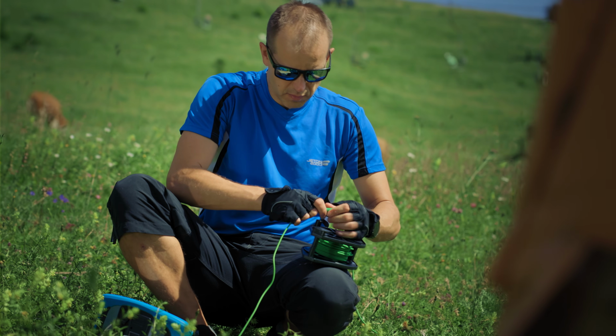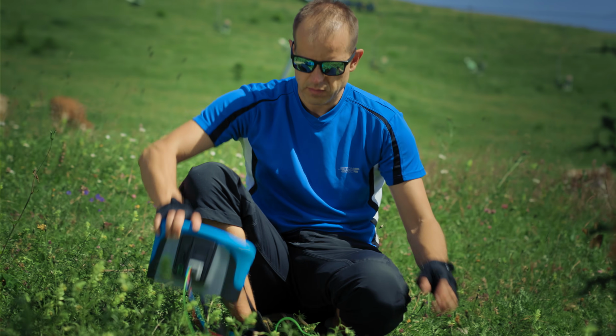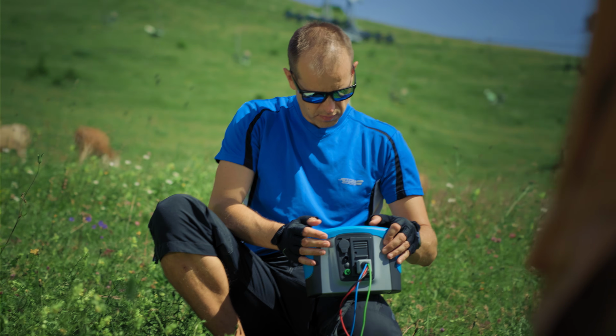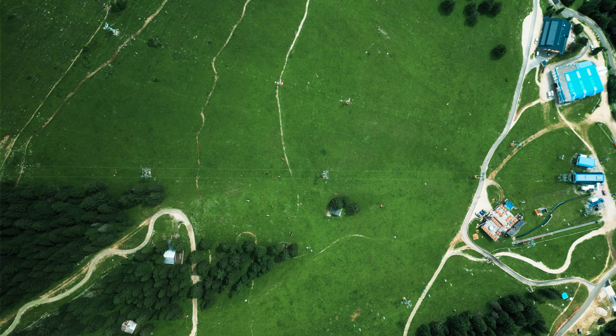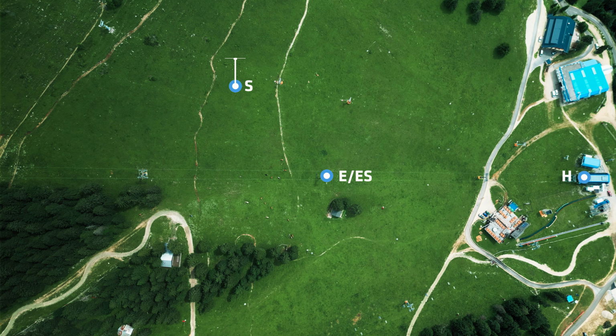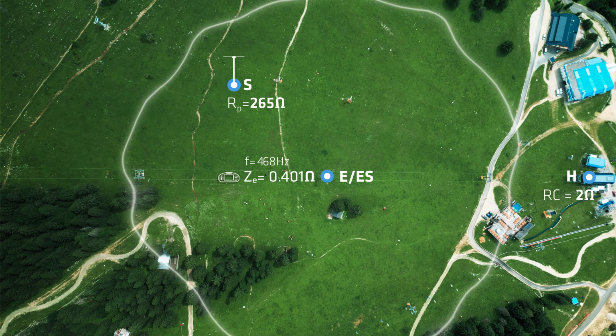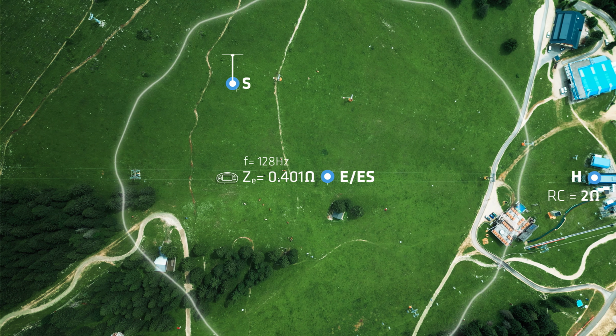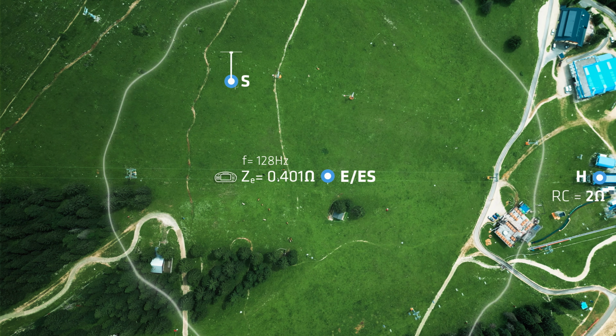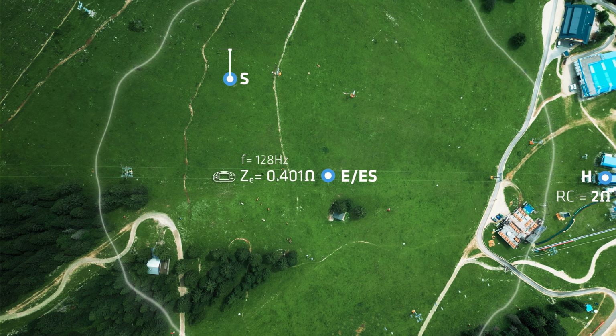Next, we apply the Earth 4-point method by placing the probe 30 to 50 meters away from the tower, perpendicular to the grounding path. This captures the full voltage funnel around the tower, while current flows between the tower and the remote grounding at the lower station.